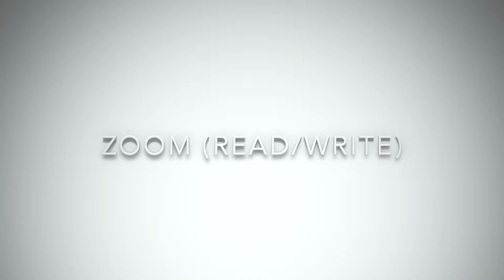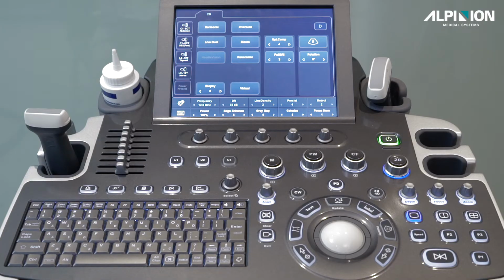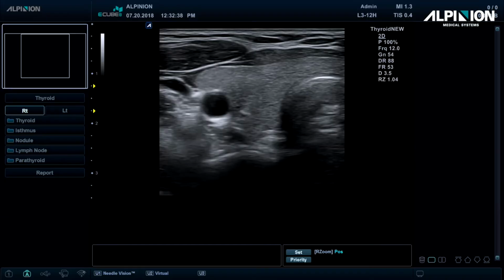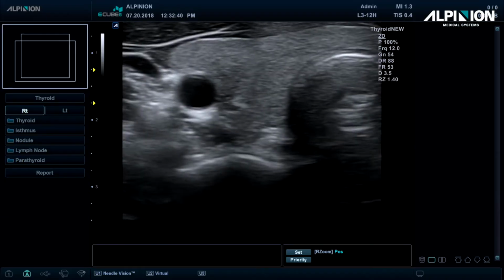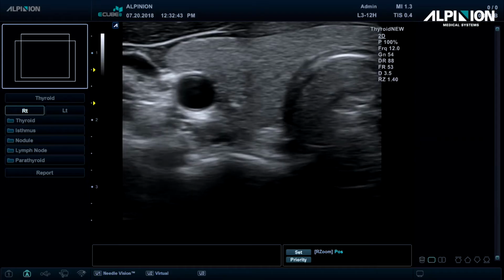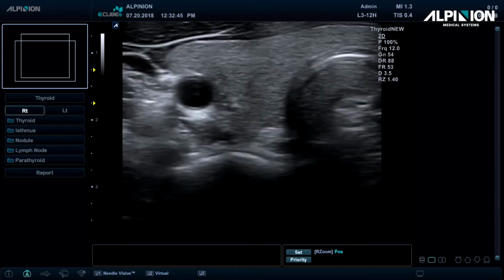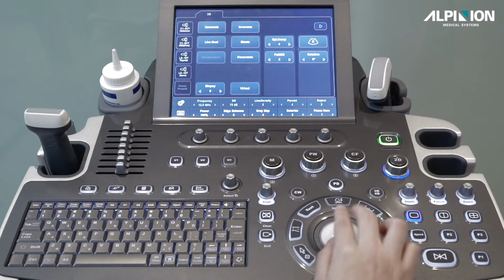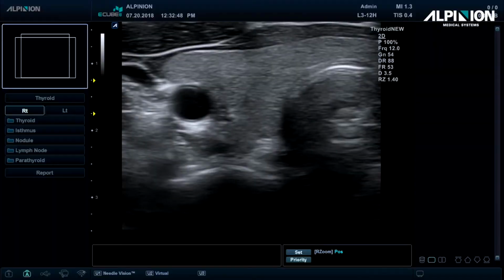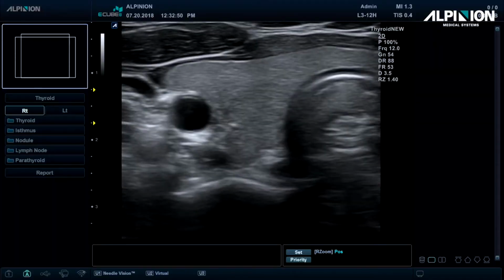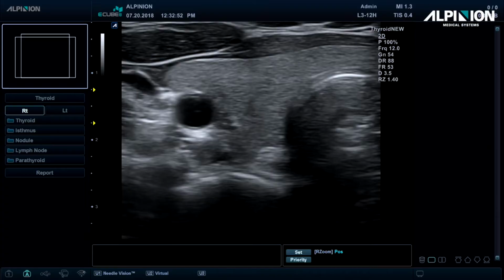Part 6. Zoom, read, write. If you need to magnify the region of your interest, you can use two types of zoom mode: read zoom and write zoom. At first, by rotating the zoom rotary key, you can simply magnify the whole image with no image improvement. This is called read zoom. By scrolling your trackball, you can move your ROI to the center of the screen while watching the location of the area in the upper left corner.